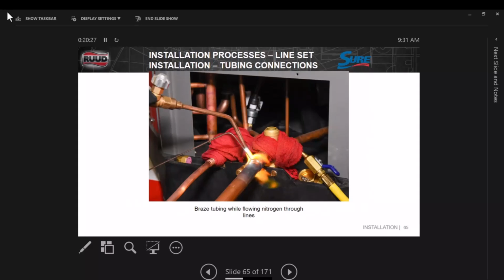We want to flow nitrogen through the lines as we're brazing. How many of us do this practice already? Oh, guys, I want to see that hand. Because if you don't, you know all that black stuff that's on the outside? That's on the inside too. Absolutely. Okay? And what did I say what this oil was in this unit? A solvent. It's a cleaner. So as it flows through this system, what's it going to do? Shine it up pretty clean, right? It's going to be real pretty in there. And flush it straight to all your orifices.